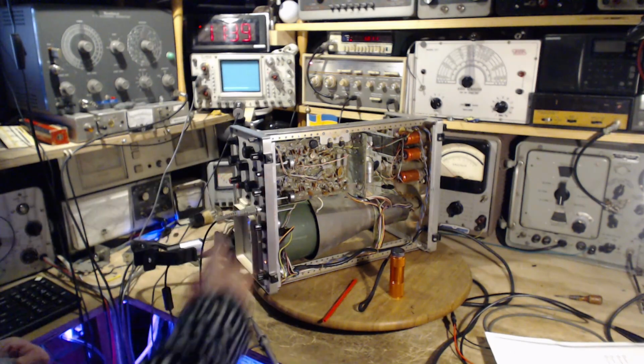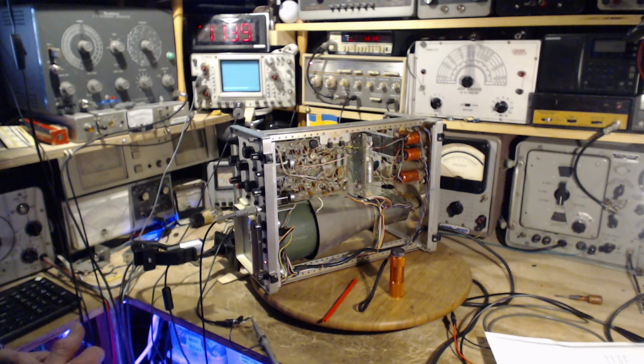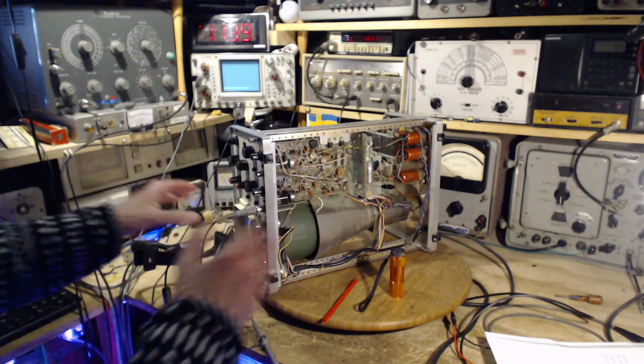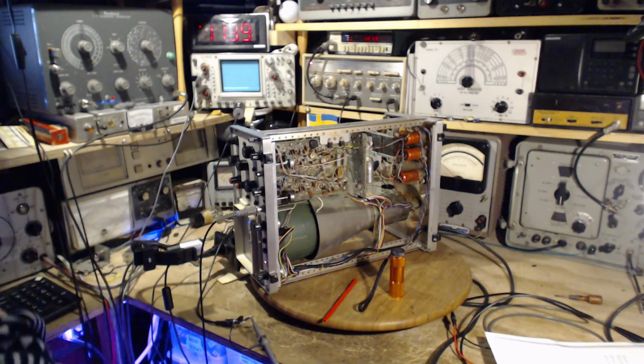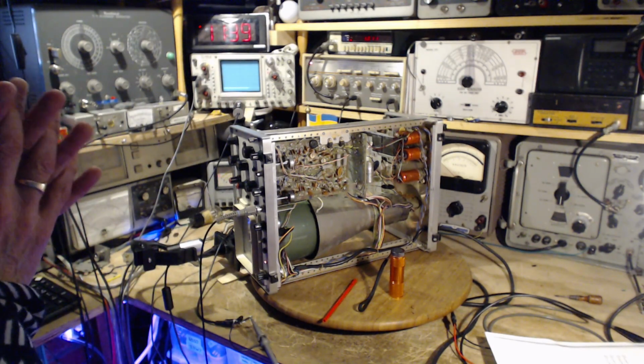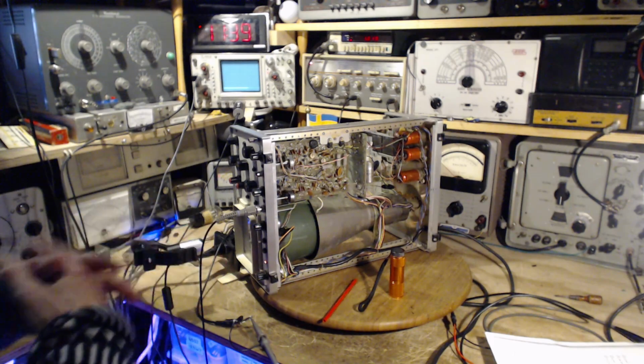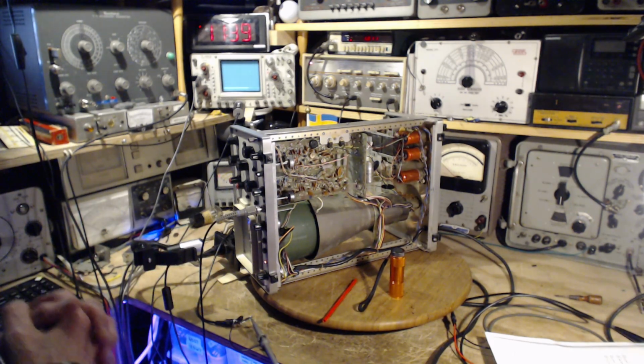So I hook up the 1 volt standard, make the adjustment. At this point, that should just show 1 volt on the front. I've essentially done that by using this as a standard. So really, all I should do is just make the adjustment of the calibrated output.